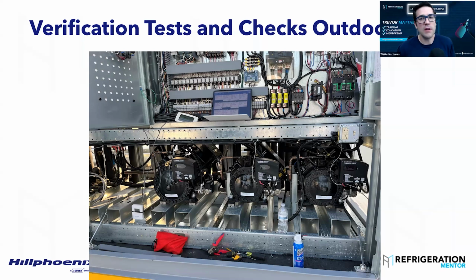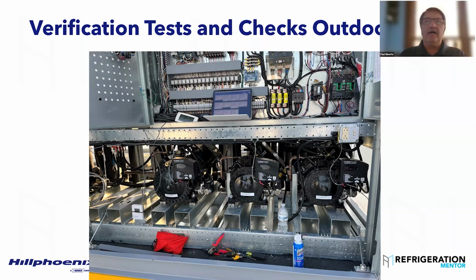Okay. Do you want to elaborate on that? Yeah, originally we spec'd Coleman grade, refrigeration grade, instrument grade, laser grade CO2 for our system. It's 99.999% pure. After the pandemic, there was an issue with a couple of the manufacturing plants. Alabama was shut down for maintenance. Mississippi plant found acetone in their water and had to figure out how to get rid of that before they could start producing CO2 again. So it was a shortage. We lowered that percentage to a 99.9.